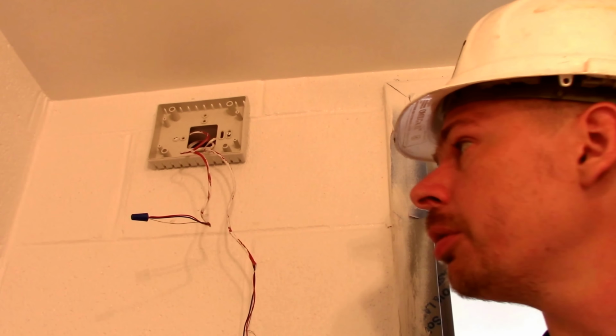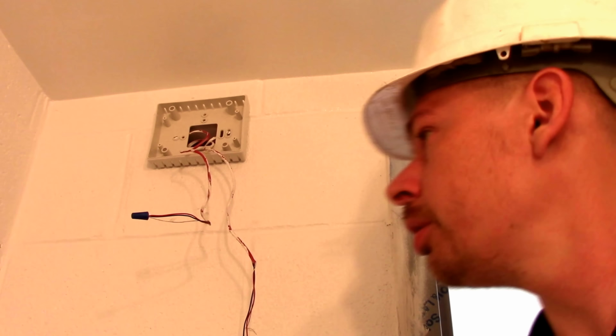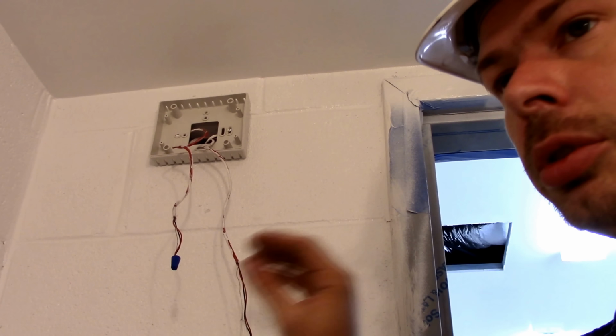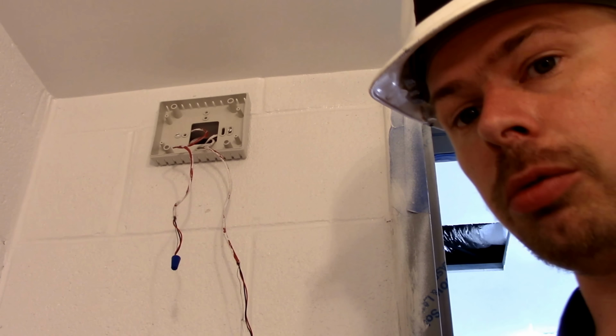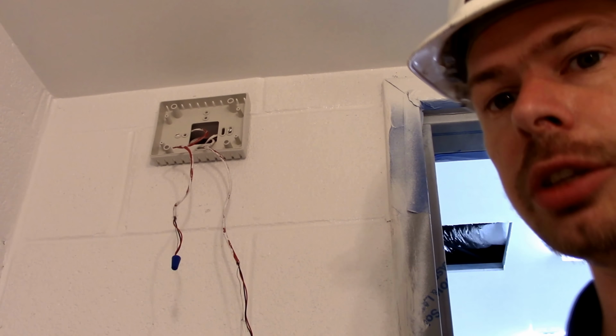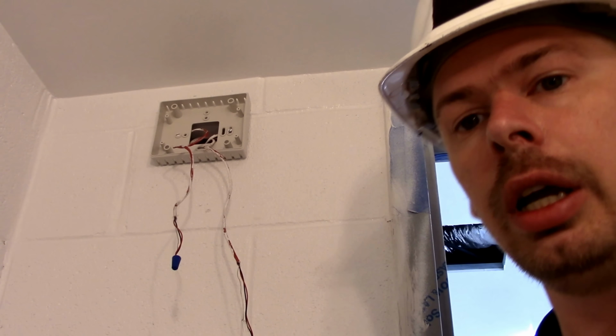Okay YouTube, I'm going to show you what's going on right here. This is two different shielded wires. It'll work, but I would have preferred one shielded wire and one thermostat wire, 18/8. That way if we have any trouble in the future, we can go back and resolve it. But with this setup, it's impossible to do unless you replace a wire - if a wire inside the walls breaks, or somebody cuts a wire in the wall or anything like that.